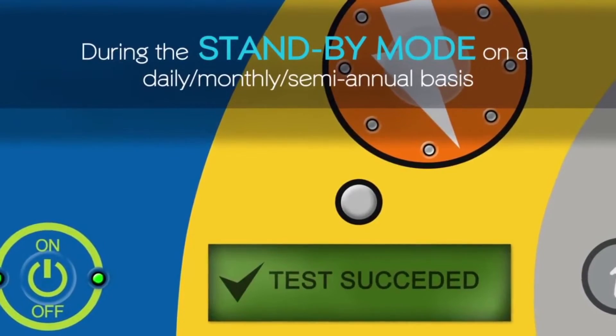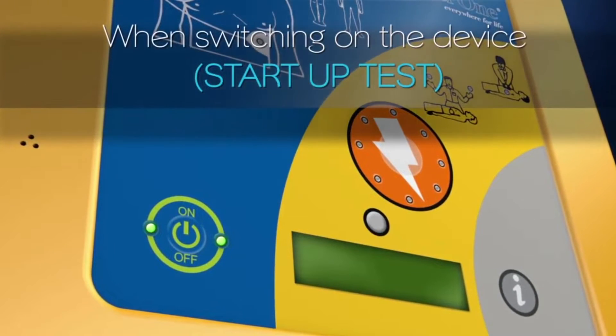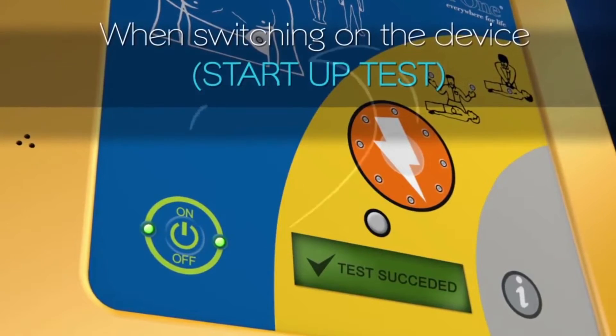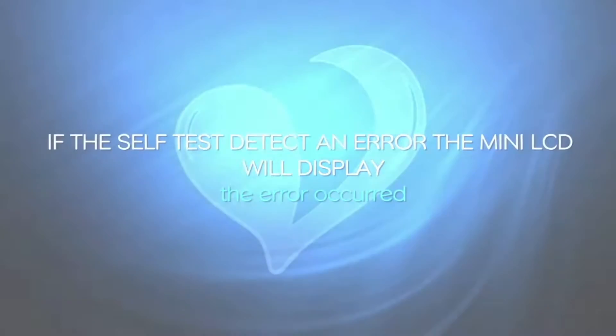When you turn on the device, the SAVA1 automatically performs a self-test — the start-up test. If the test is successful, 'Test succeeded' will be displayed on the mini LCD screen.